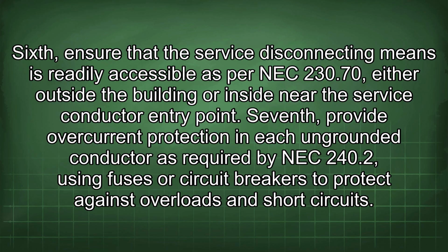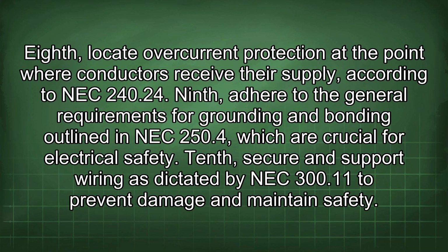Seventh, provide overcurrent protection in each ungrounded conductor as required by NEC 240.2, using fuses or circuit breakers to protect against overloads and short circuits. 8. Locate overcurrent protection at the point where conductors receive their supply according to NEC 240.24. 9. Adhere to the general requirements for grounding and bonding outlined in NEC 250.4, which are crucial for electrical safety. 10th. Secure and support wiring as dictated by NEC 300.11 to prevent damage and maintain safety.